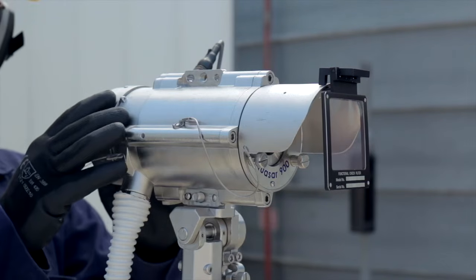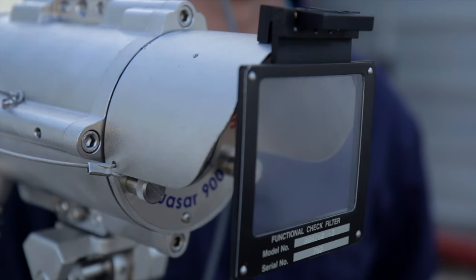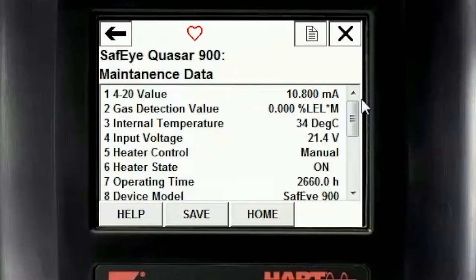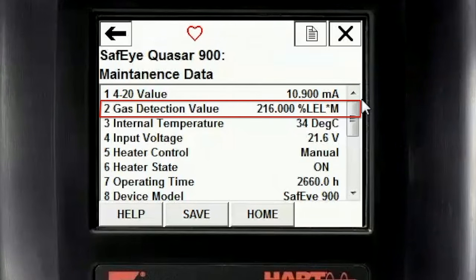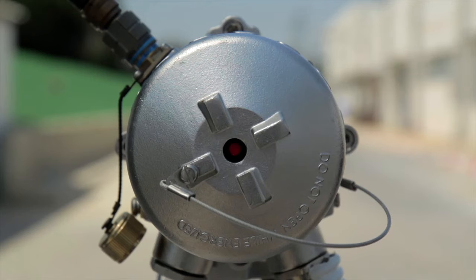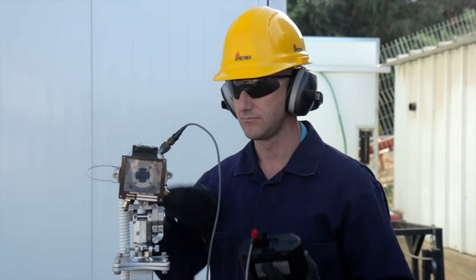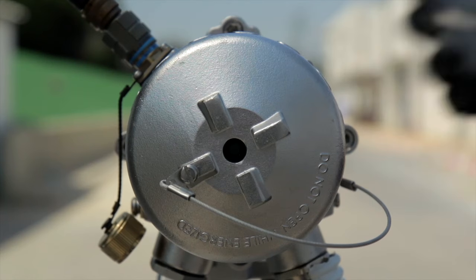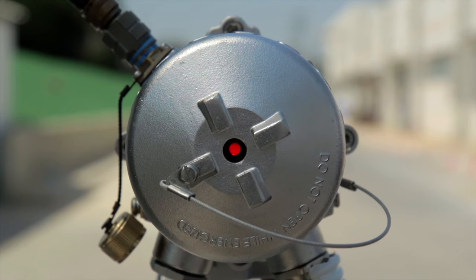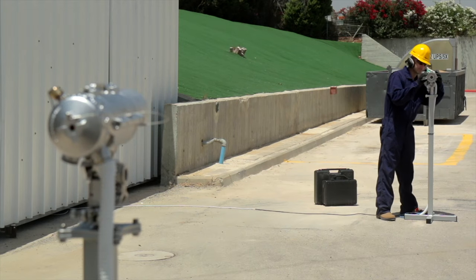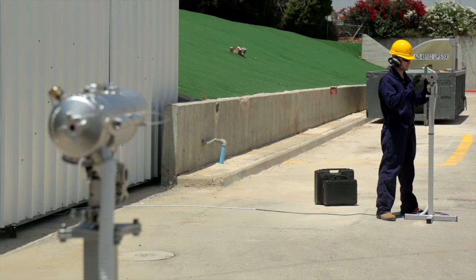The filter must be centered over the detector's viewing window. Then, wait for 20 seconds and read the LEL value on the HART maintenance screen and verify that a blinking red warning status appears on the back of the receiver. Repeat this step with the alarm functional check filter and verify that a solid red alarm status appears on the back of the receiver. The Quasar 900 does not require calibration and needs minimal maintenance during its long lifetime.